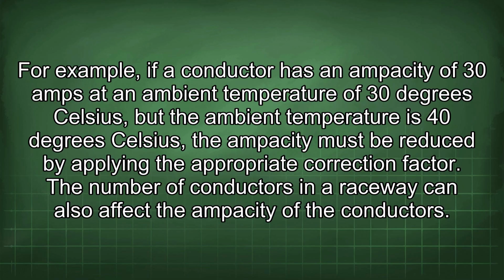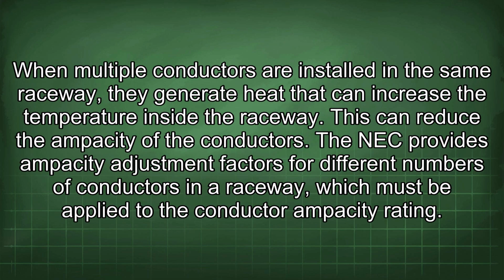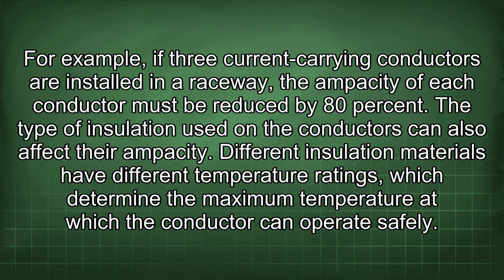The number of conductors in a raceway can also affect the ampacity of the conductors. When multiple conductors are installed in the same raceway, they generate heat that can increase the temperature inside the raceway. This can reduce the ampacity of the conductors. The NEC provides ampacity adjustment factors for different numbers of conductors in a raceway, which must be applied to the conductor ampacity rating. For example, if 3 current-carrying conductors are installed in a raceway, the ampacity of each conductor must be reduced by 80%. The type of insulation used on the conductors can also affect their ampacity.